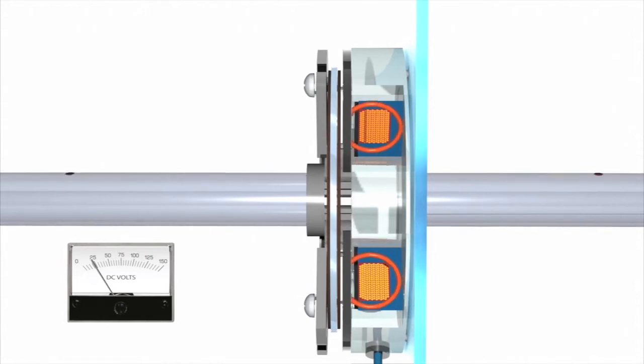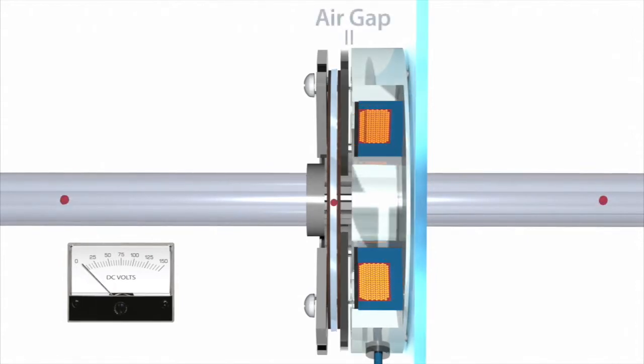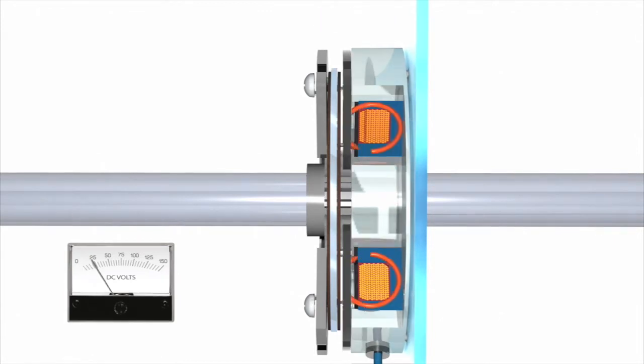When power is removed from the coil, the pressure plate is released and the springs push the pressure plate against the friction disc, trapping it between the pressure plate and the outer brake cover plate.